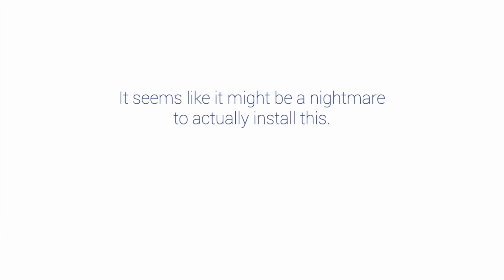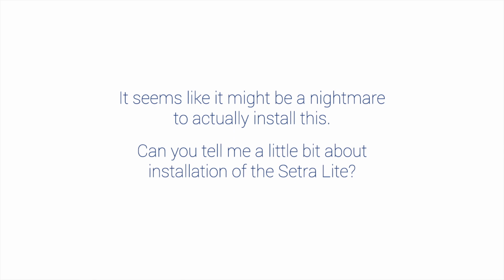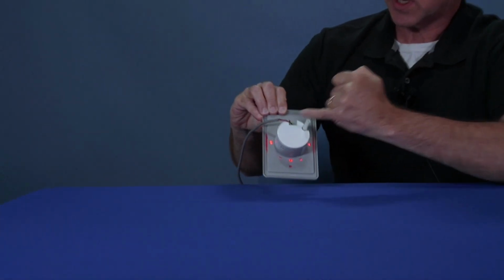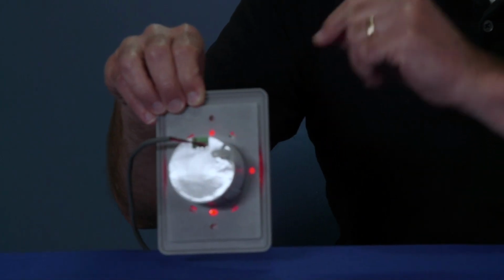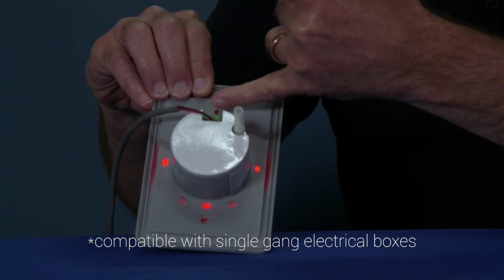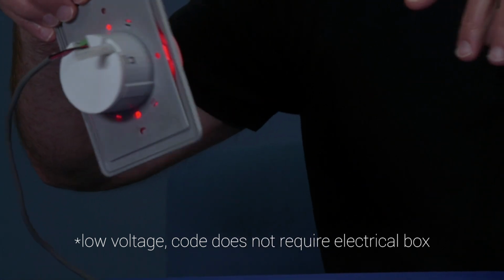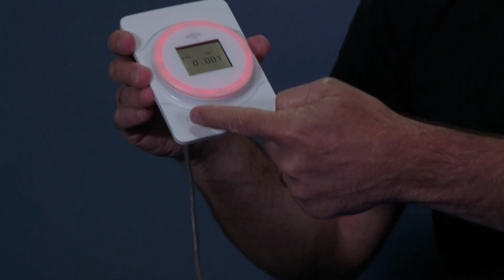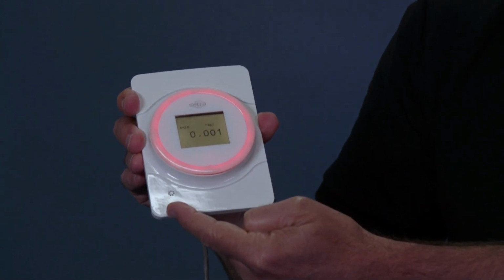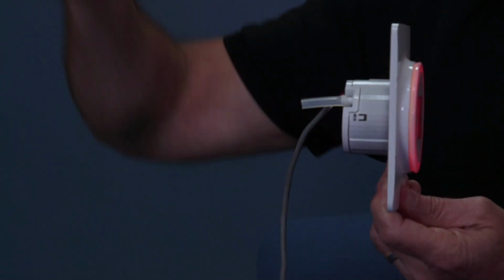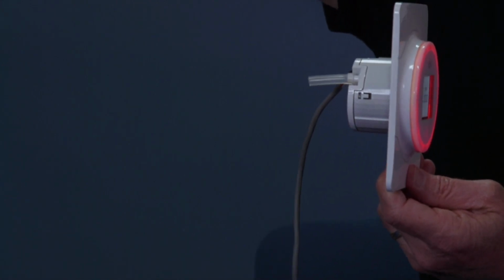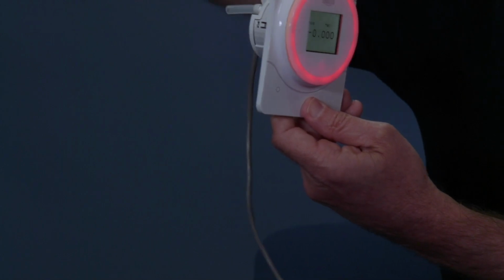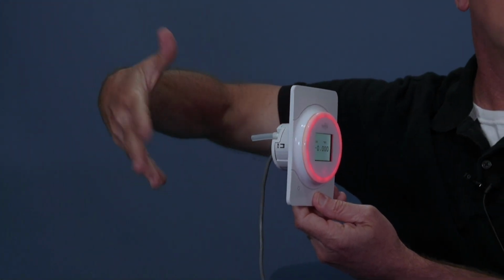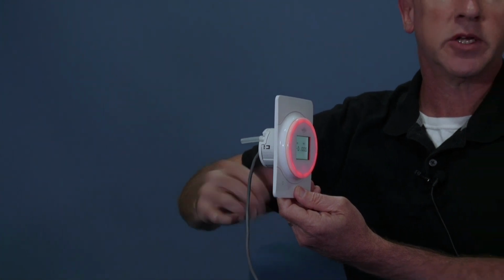Jeff, I love the product, but it seems like it might be a nightmare to actually install this. Can you tell me a little bit about installation of the Setra Lite? If you can see back here, we actually have a screw hole. So this is easy to install in a single gang box, or just use sheetrock screws and directly attach this to the wall. Also, from an installation perspective, one of my pressure pickups is right here on the front panel. And then the other pressure pickup, we can run one of our snubbers up through, oftentimes it might be a ceiling tile or maybe just the back end of the wall, depending upon where and how a customer wants to install the product. A little bit of flexibility, but very easy to install.